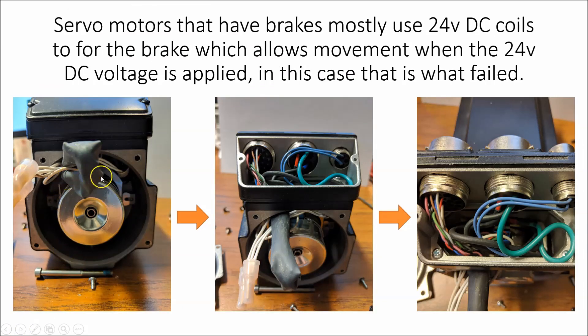This picture shows the bolts taken out of the outside ring that holds the encoder. That ring holds it from moving left to right. You have a center bolt that holds it in place and then the outside ring that holds it from moving left and right.